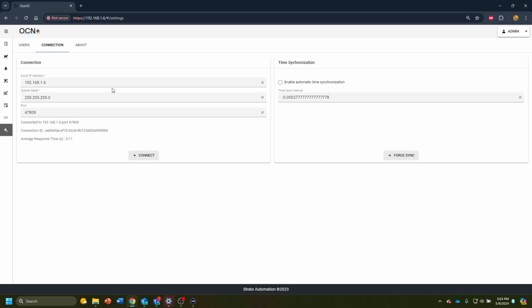Now to begin adding devices, first I'm going to set up my connection. Here I'm going to enter my local IP address, matched up with the IP address of my Ocean server, and the subnet mask matches up as well. I've selected port 47808 to match up with the network my BACnet routers are on.